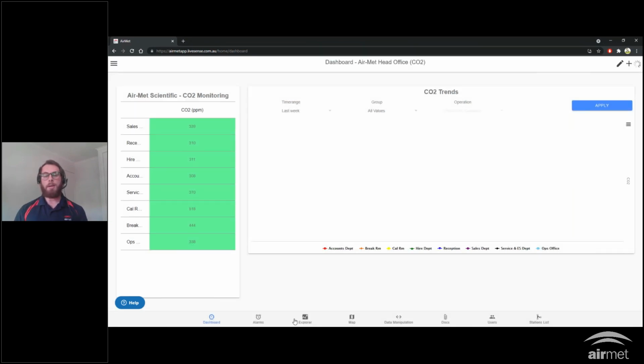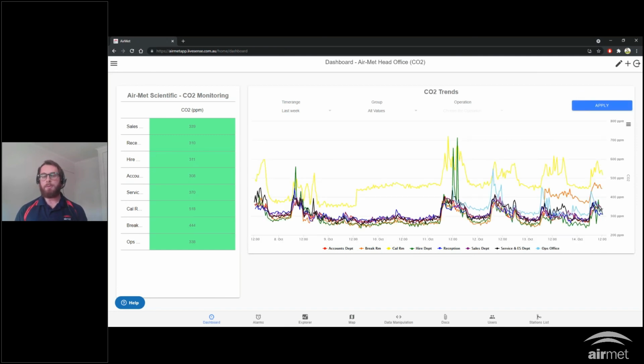From this adjustment, you can quite clearly see some trending data, and we can further identify periods of potential concern. Although we are only seeing spikes of 600 to 700 ppm, we are at minimal capacity in the office, as most would be at this stage, and this could potentially increase with the return of staff later in the year. So for our example, perhaps further investigation into these areas is required to address the potential future issues.